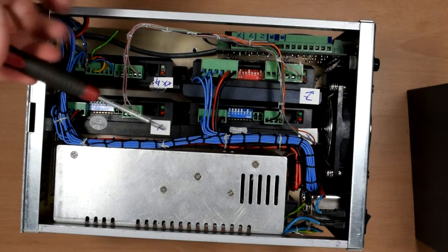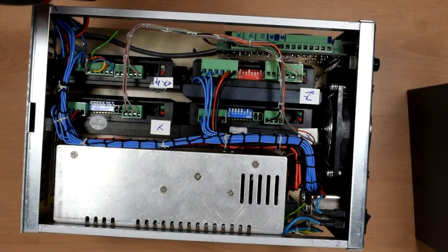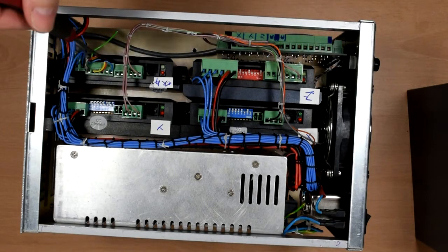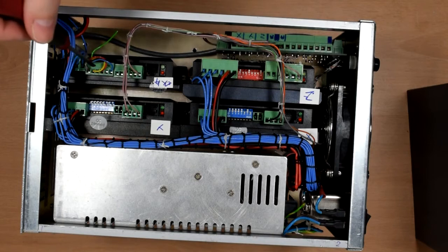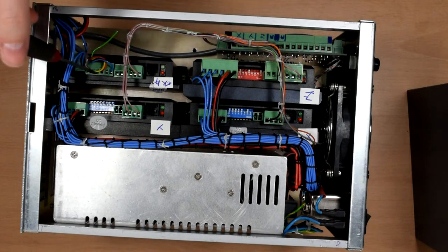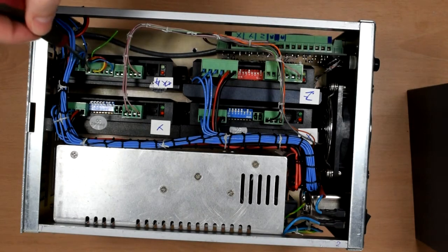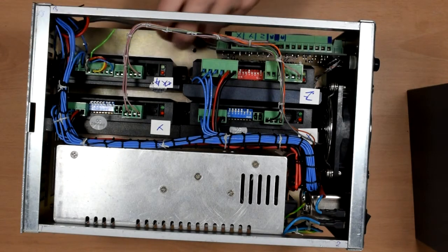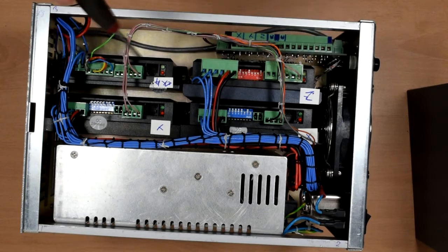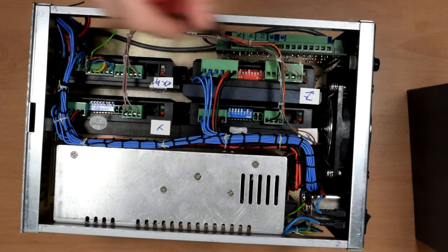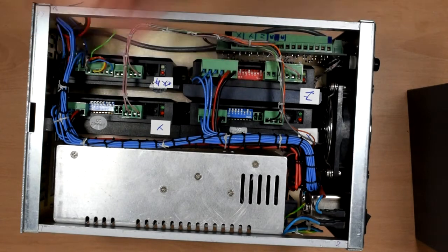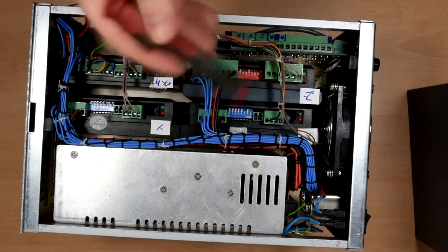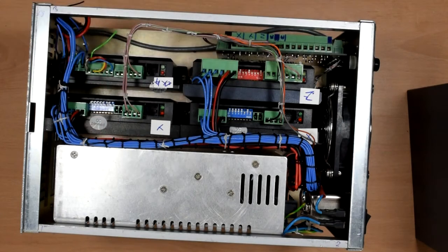Particularly in the encoder lines, if you have any kind of servo motor with an optical encoder on the back of it, be very very careful routing the lines from that and use shielded cables. I actually use a shielded cable here. In fact, ideally use shielded cables for all the signaling because these things are just impossible to control the RFI otherwise.